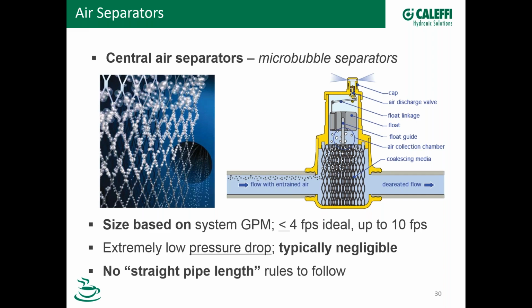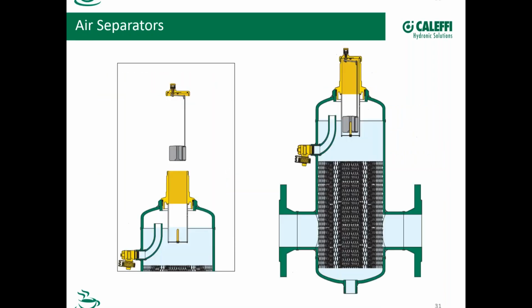Another question that has come in is, are there requirements for straight pipe lengths upstream or downstream of an air separator? And the answer is no. They don't require that. Straight pipe lengths are typically applied when you are measuring flow, like in a flow meter or a differential pressure sensor of some type, but this device doesn't need that.